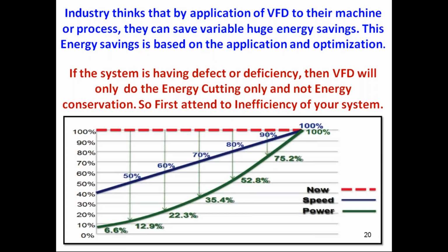As I was telling you, when you go to the industry, let us have a direct line of demarcation. What are constant torque loads? What are variable torque loads? Variable torque loads will give you a lot of energy savings. You concentrate on that. Many people think VFD and install the VFD, but the industry is using the VFD only for variable speed application. When they want to change the pulley ratio, they just operate the VFD at 48 hertz or 46 hertz or 45 hertz instead of 50 hertz. But that is not the purpose. We want to use the VFD for a better purpose. It has to give you better operation and energy saving also. Next, please.